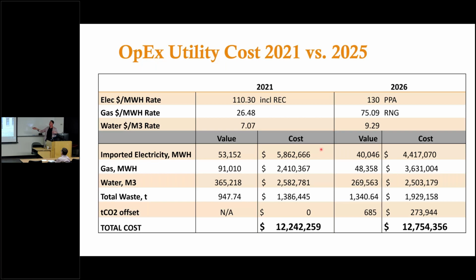And water continues to cost more as it becomes a scarcer, more intermittent resource. But you can see here how much we reduced our electric use. You can also see, because of a steam study and maximizing use of the boilers at one site, we went from 5 boilers - 2 with pneumatic controls, 3 with digital - to getting rid of the 2 older pneumatic ones. The steam study found that instead of running all 3 boilers all winter and 2 all summer, we only needed 1 boiler at 60-70% for 7 months of the year, plus a second boiler even in the coldest months.